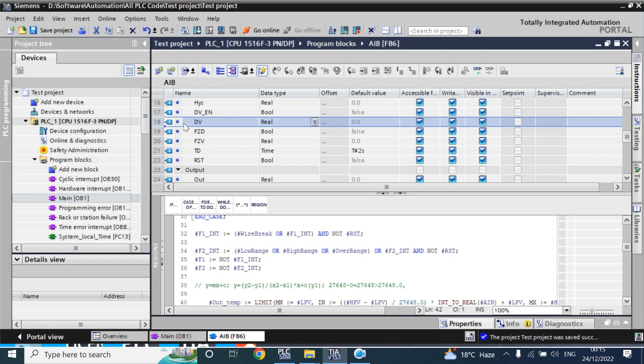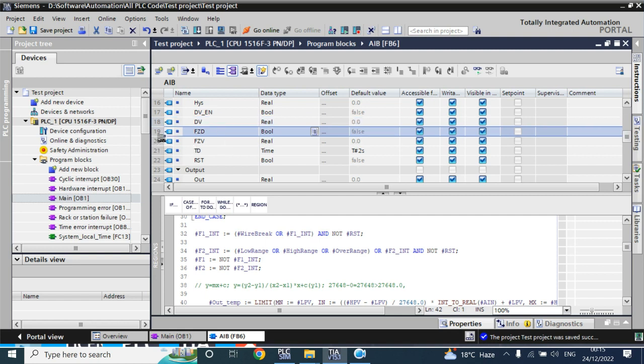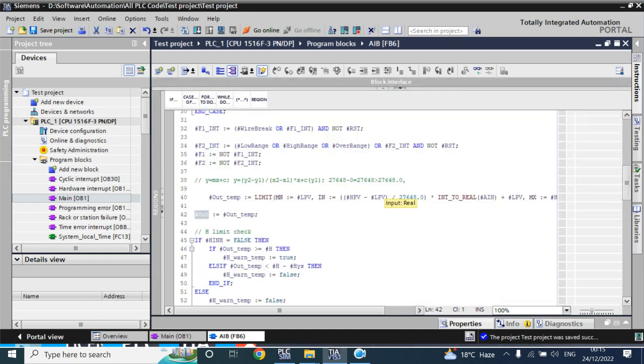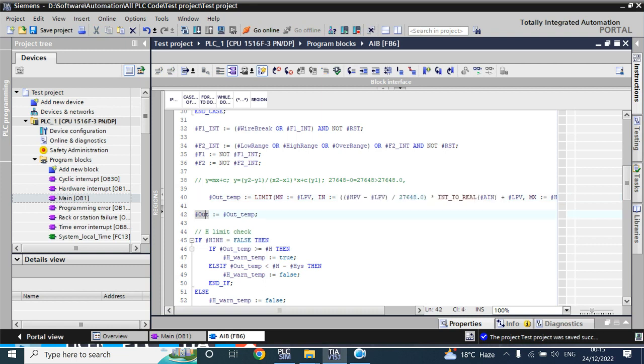The second case is for maintenance purpose — if you choose the freeze option, it will take the output from the frozen value. The third option: it will take the input from the analog sensor, convert it using the linear line equation, and copy the result to the output.